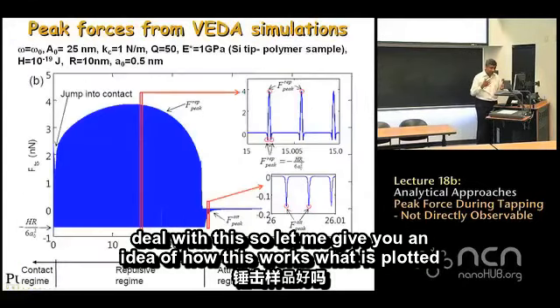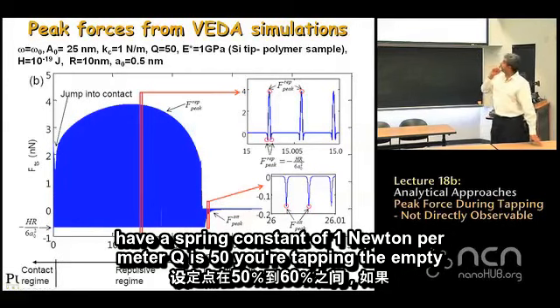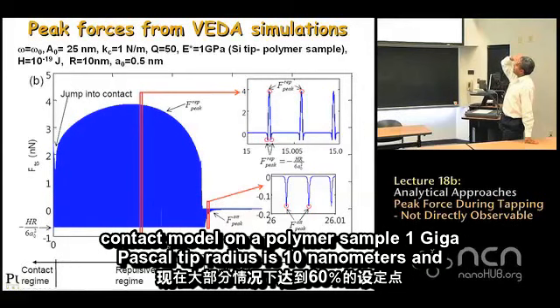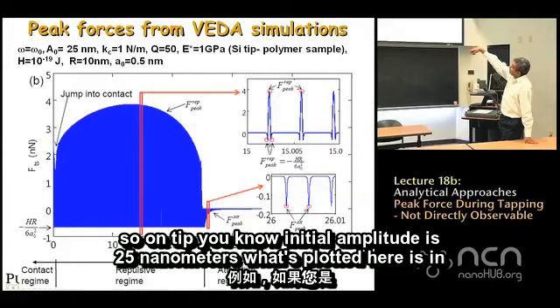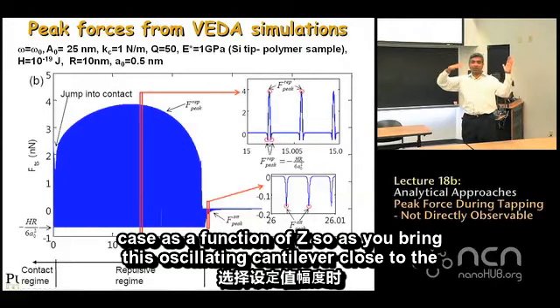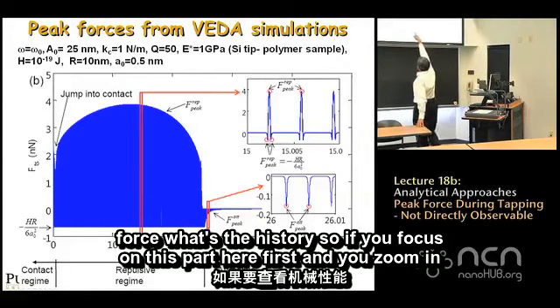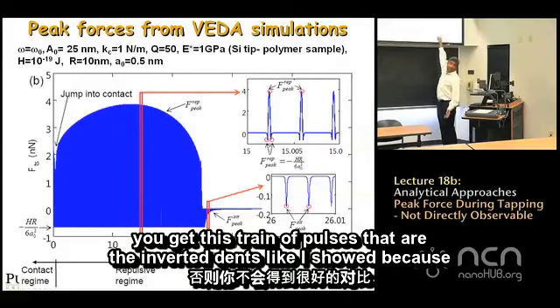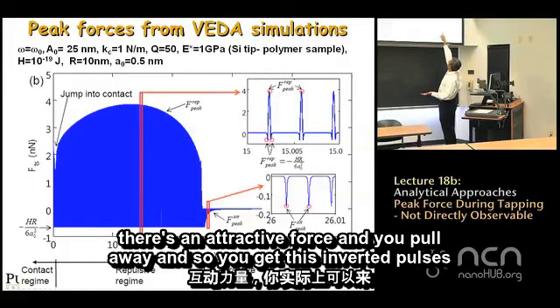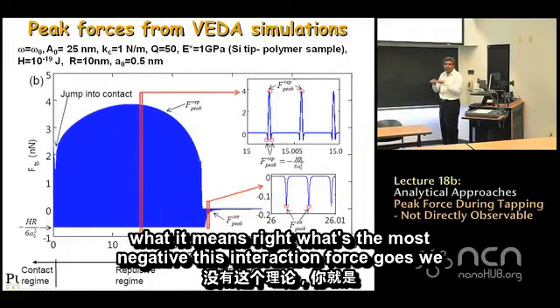A simulation was done in VEDA with parameters: spring constant of 1 N/m, Q of 50, DMT contact model on a polymer sample of 1 GPa, tip radius 10 nm, initial amplitude 25 nm. What's plotted is the history of tip-sample interaction force as a function of z as you bring the oscillating cantilever close to the surface. Focusing on the region far from the surface, you get a train of inverted pulses because you're in the attractive regime — we call this F attractive peak.